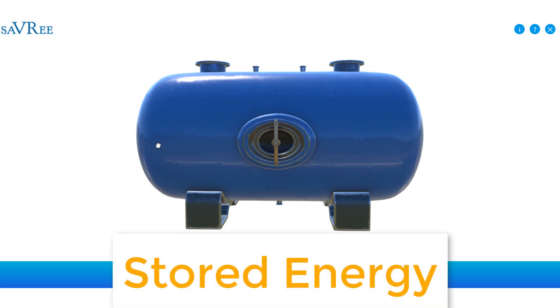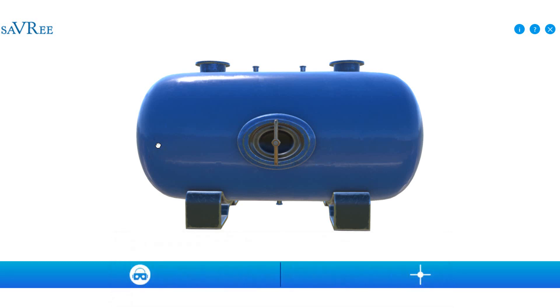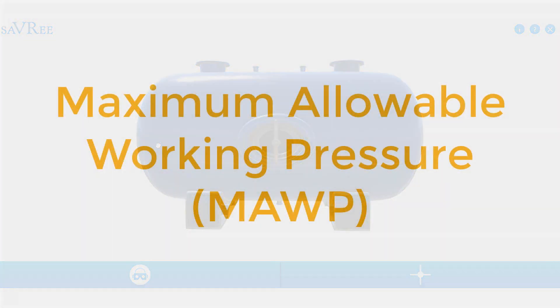Now it's all fine when we're operating between six and eight bar because it might have a design limit or a max allowable working pressure of 10, 12, or 14 bar. So we're well within limits if we're storing air at eight bar.